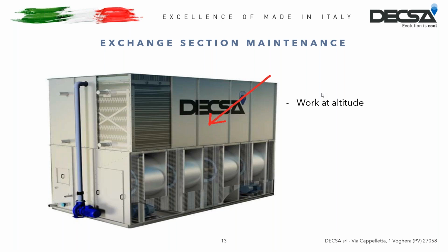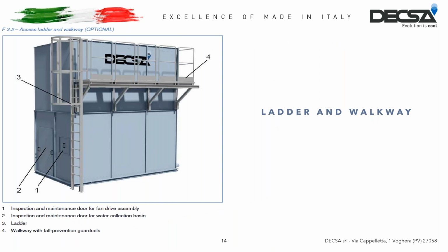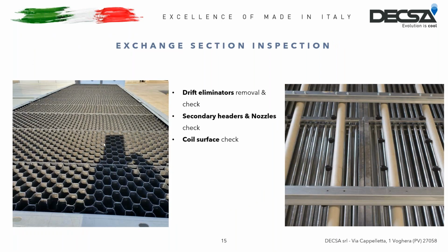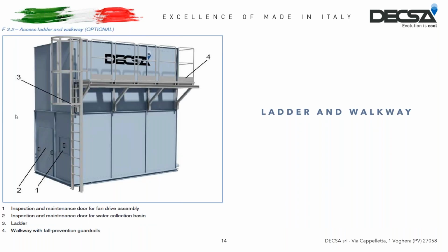Now we proceed with the inspection of the exchange section. To do this, it's necessary to reach the drift eliminators. If there is no ladder with platform installed on the unit, a component that we supply on request as an option with a new unit or as a spare at any time, it's necessary to use a lifting platform with all the necessary protection and safety devices. I mean safety belts, helmet, etc.